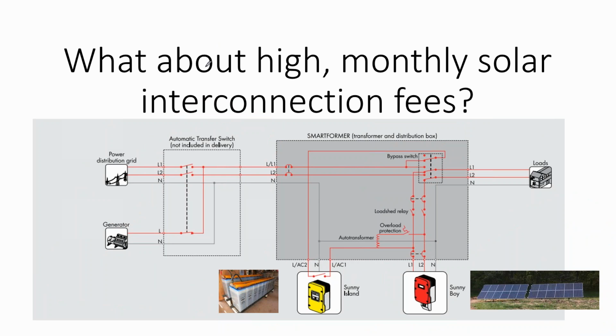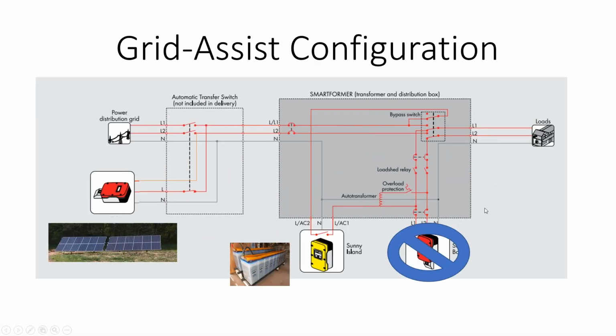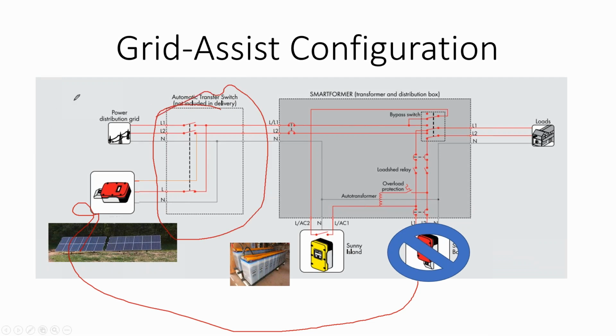So there's an interconnection called grid assist that's used under punitive, anti-solar rate structures. I thought this would be more of an issue when writing the program, but I haven't really seen a US application for it — it's more popular in Australia. Basically, they take the solar array and land it on a transfer switch so that either the grid is feeding the home or the solar array is feeding the home, but not at the same time.